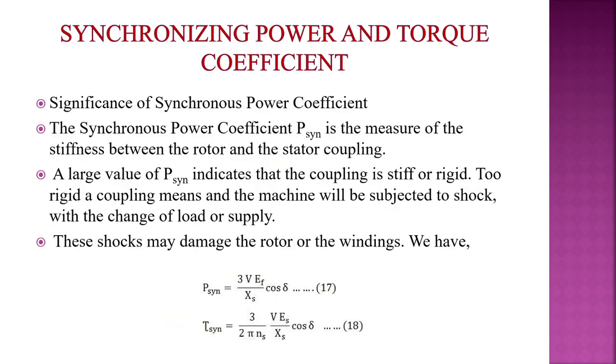Let us see the significance of synchronizing power coefficient. It is a measure of the stiffness between the rotor and the stator coupling. A large value of P syn indicates that the coupling is stiff or rigid. Too rigid a coupling means the machine will be subjected to shock with the change of load or supply. These shocks may damage the rotor or the windings.